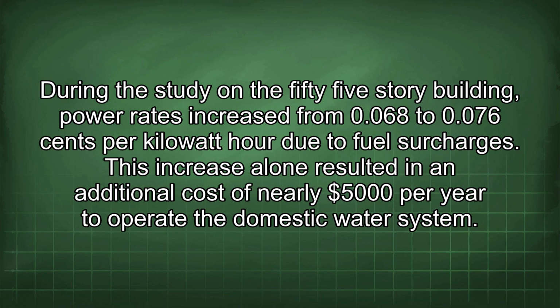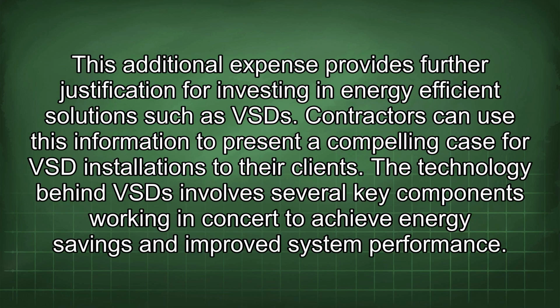During the study in the 55-story building, the power rate increased from 0.068 to 0.076 cents per kilowatt-hour due to fuel surcharges. This increase alone resulted in an additional cost of nearly $5,000 per year to operate the domestic water system. This additional expense provides further justification for investing in energy-efficient solutions such as VSD. Contractors can use this information to present a compelling case for VSD installations to their clients.